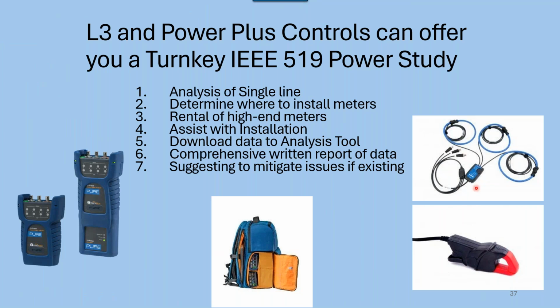If it's a low voltage system, I've got Rogowski coils, so we can put them right around the conductors. If it's a medium voltage system, these Rogowski coils are not designed for high voltage. So I'm going to need to get to the secondary, and I can use a clamp-on ammeter and plug that into the meters. And we're measuring both the voltage and the currents.